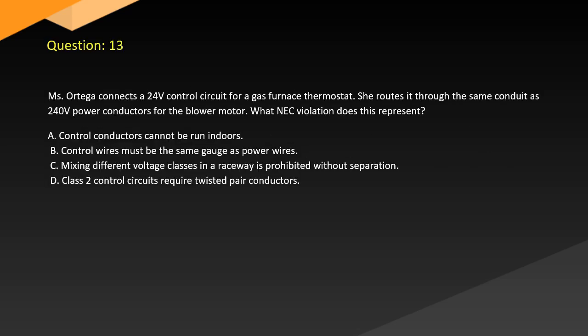Question 13. Ms. Ortega connects a 24 volt control circuit for a gas furnace thermostat. She routes it through the same conduit as 240 volt power conductors for the blower motor. What NEC violation does this represent? A. Control conductors cannot be run indoors. B. Control wires must be the same gauge as power wires. C. Mixing different voltage classes in a raceway is prohibited without separation. D. Class 2 control circuits require twisted pair conductors.